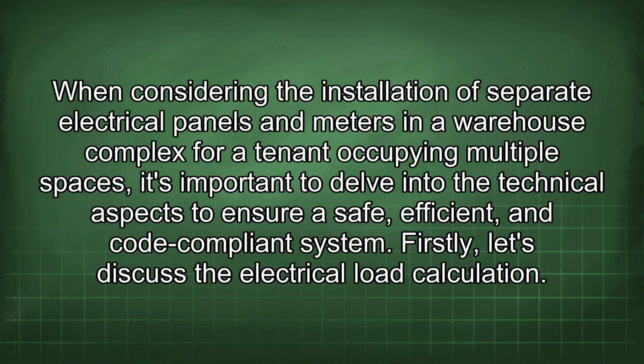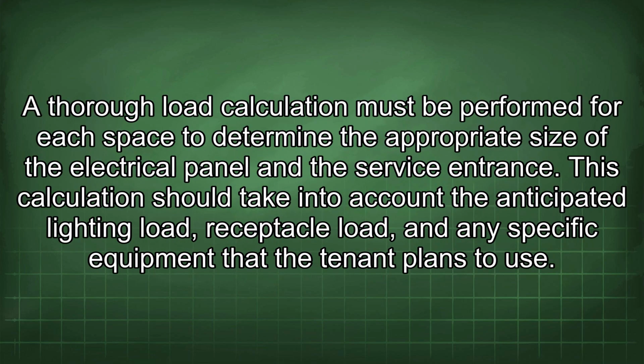When considering the installation of separate electrical panels and meters in a warehouse complex for a tenant occupying multiple spaces, it's important to delve into the technical aspects to ensure a safe, efficient, and code-compliant system. Firstly, let's discuss the electrical load calculation. A thorough load calculation must be performed for each space to determine the appropriate size of the electrical panel and the service entrance. This calculation should take into account the anticipated lighting load, receptacle load, and any specific equipment that the tenant plans to use.